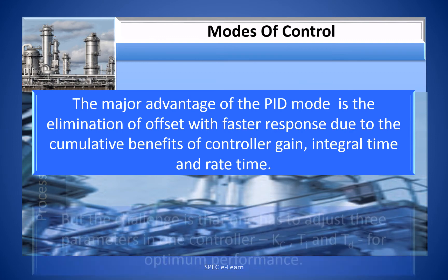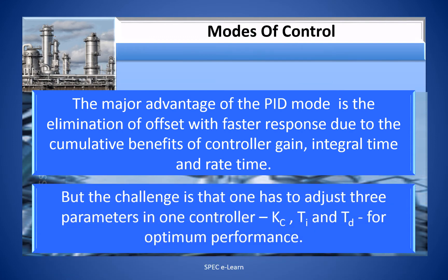The major advantage of the PID mode is the elimination of the offset with faster response, due to the cumulative benefits of control gain, integral time, and rate time. But the challenge is that one has to adjust three parameters in one controller — Kc, Ti, and Td — for optimum performance.